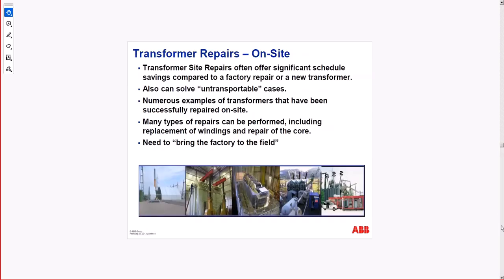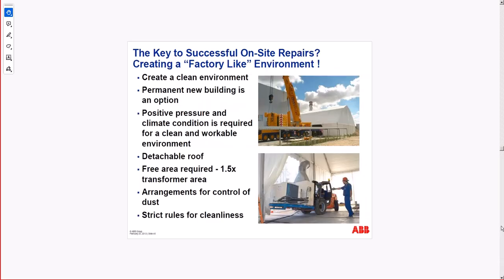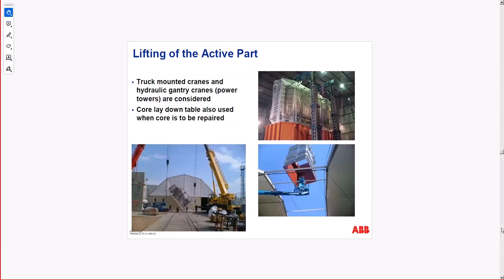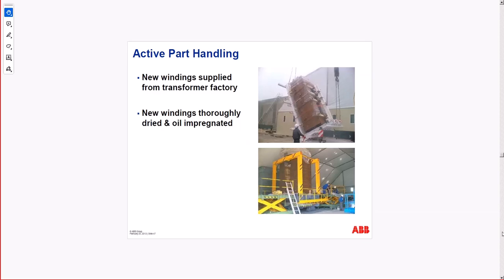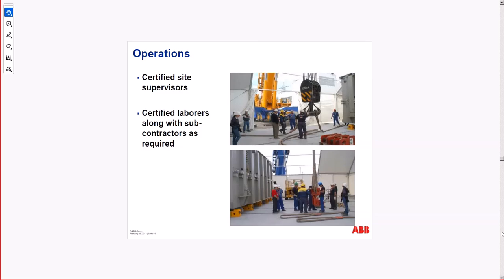Repair examples, here are more of that, more on-site and off-site repairs. Key to the success of the site repairs is creating a factory-like environment around, a free area, and all the procedures apply the same as in the factory with no dirt or ingress. Testing at the end of the repair is mandatory, the same tests that you do for a new transformer. Active part handling, you see the operations. Certified site supervisors from ABB need to review and supervise this kind of operation. Nobody in Bruce or OPG or any plant is qualified for this work on site. They will come from ABB or from the other manufacturer that is the manufacturer of the transformer. So they are specially qualified to oversee and supervise the process of repair on site.